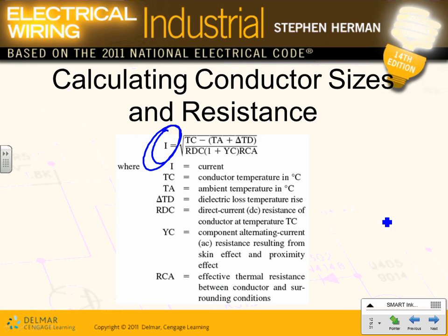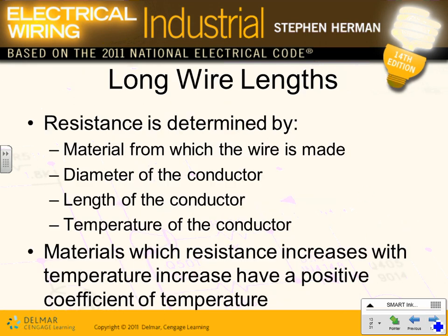You can use this formula to find the rate based on the temperature instead of using the table. So either use this formula or you use the tables. 99.9% of us use the tables because we don't have software. Okay, the second thing, guys, so this is the ampacity.